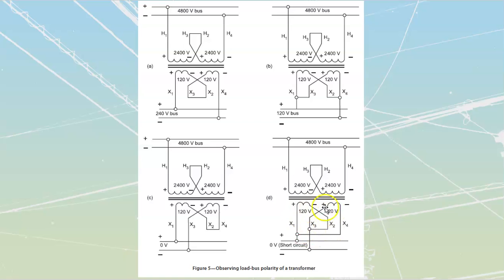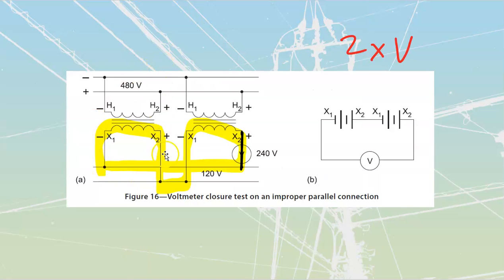The connection that we have made right now is actually entirely equivalent to this one that they had over there, but we're just making it using now 2 transformers that are single winding instead of 1 transformer that's double winding inside of there. It's going to be a terrible, terrible value of voltage to have. So I'm going to disconnect. If I'm reading that high amount of voltage, we disconnect that. We then reverse the connection. And then we are going to once again do the voltmeter closure test. Okay, voltmeter closure. You can remember the whole thing as 0 to about half voltage, probably good. Double voltage, 100% bad. Guaranteed that that thing is going to be bad.